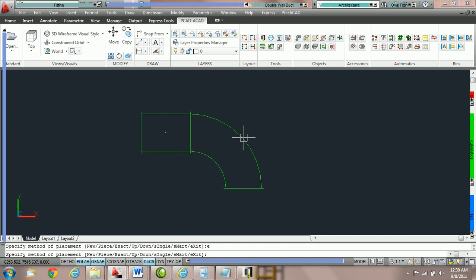So this is a way of preventing yourself from putting a piece of duct on the drawing that's too small. Often you might want to say that the minimal leftover will be 6 inches. And then once you see that PractiCAD won't fill in the gap because it won't put a 6-inch piece, we would switch it to Smart Route or M, where it would extend the straights of the elbow for us. So this is a good method for using minimal leftover.